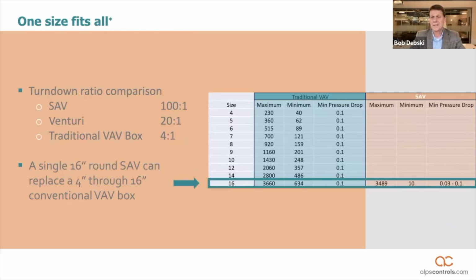One size fits all, asterisk. We'll talk about that here in a little bit. But because of that level of accuracy over a wide range of airflows, the smart air valve has a turn down of 100 to 1. If you look at the next closest product that we deal with in the industry, a Venturi air valve, has a turn down of 20 to 1. A traditional VAV box is 4 to 1. So this is a 5-time improvement over its closest competitor in the marketplace.